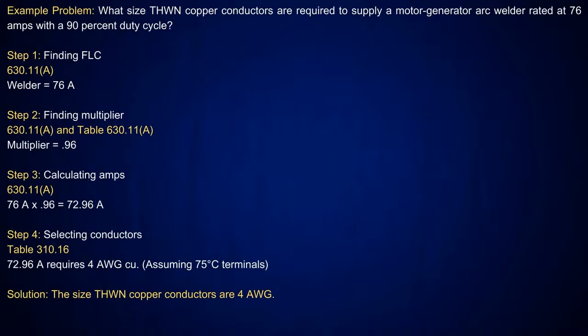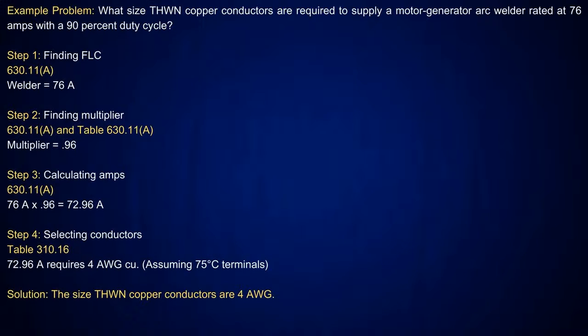So I think we had a good comment come in that Danny mentions. You know, the NEC gives you a direction to adjust ampacity if it's more than 3 current carrying conductors. So that's one thing you're going to have to really look at. Sure. And we actually did that in an earlier portion of this, probably about 3 or 4 episodes before. I went through all of that, explaining the current carrying conductors and how to do the calculation for adjustment and correction factor, or a combination of the two.